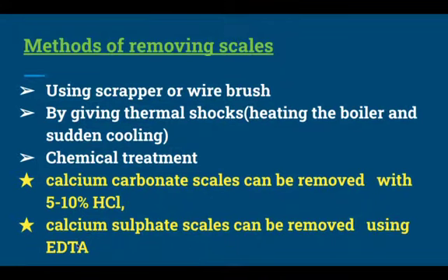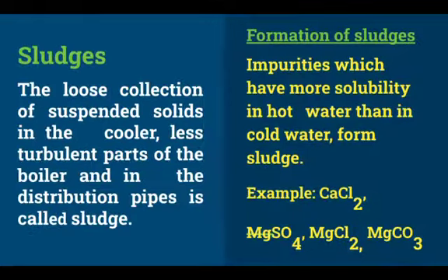Now calcium sulfate scales can be removed by using EDTA. When treated with EDTA solution, the calcium reacts with EDTA and forms a calcium EDTA complex, which is highly soluble in water, and thus these scales can be removed. So these are the methods of removing scales. Now we'll move on to sludges.